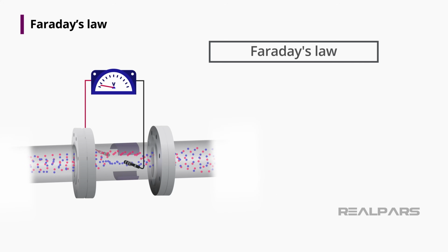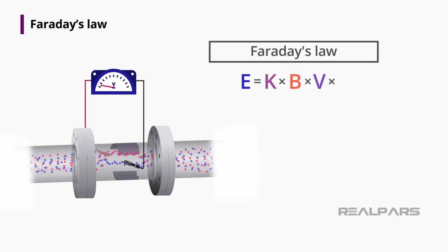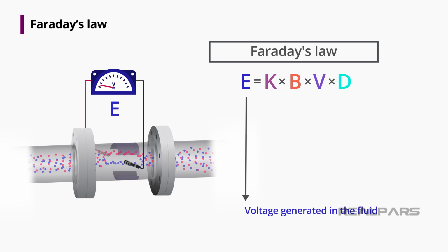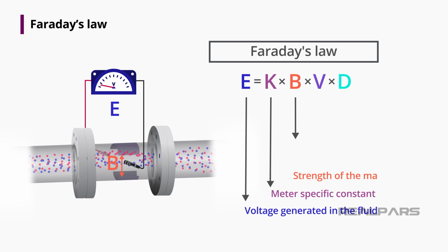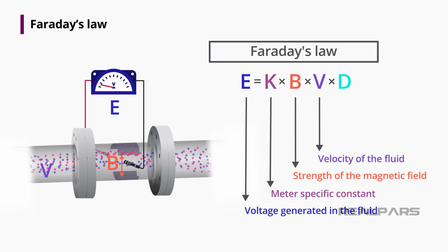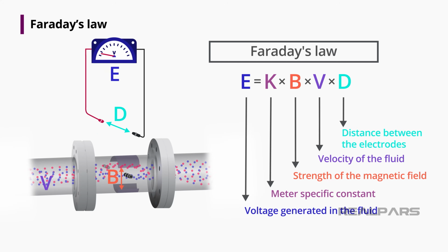Faraday's law can be expressed simply as E is proportional to K times B times V times D, where E is the voltage generated in the fluid, K is the meter-specific constant, B is the strength of the magnetic field, V is the velocity of the fluid, and D is the distance between the mag meter's electrodes.